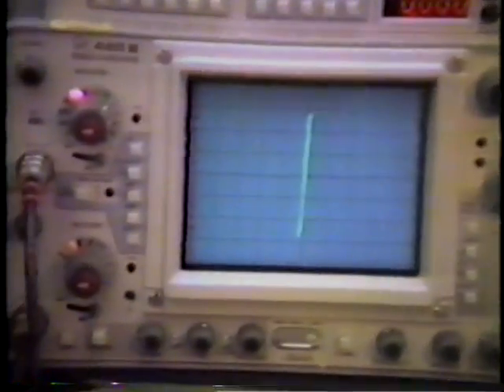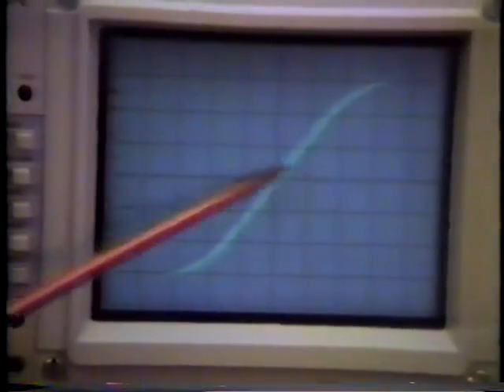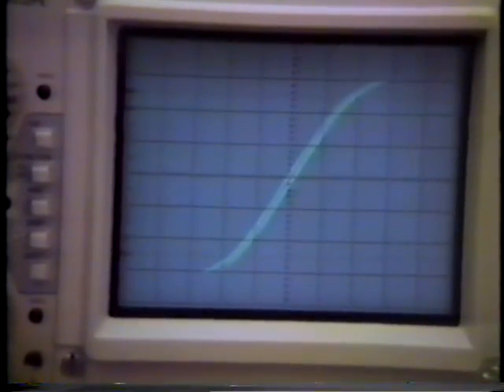We can see on the flux versus current characteristics on these traces how, by increasing the air gap, the slope of the characteristics tilts over and we can pass larger DC current without actually saturating the core. And we see that effect clearly here.